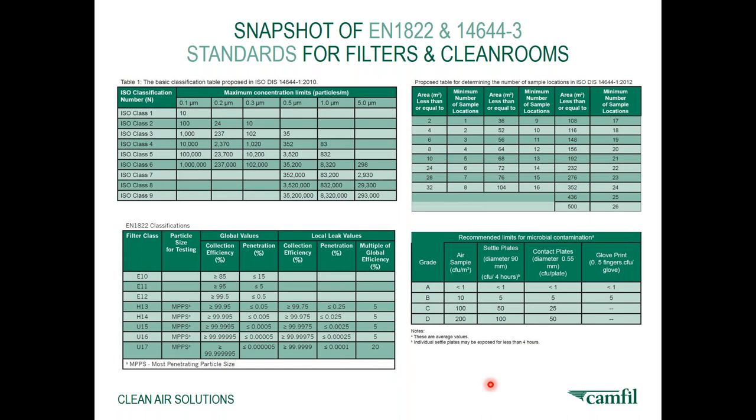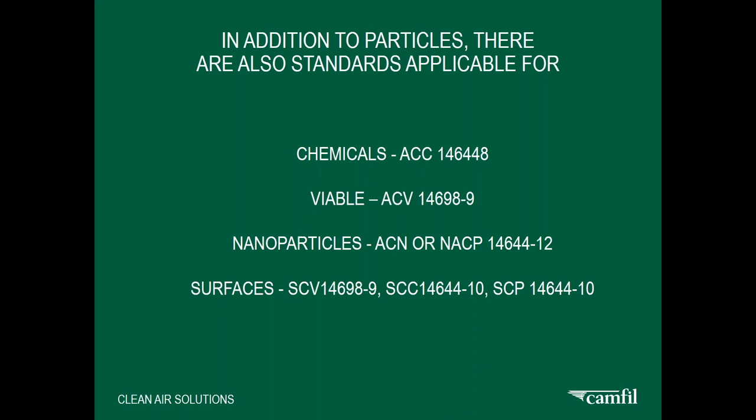Air cleaner is a perfect solution for ISO 7 to ISO 9 and where no laminar airflow is needed. Air cleaner filters are equipped with an H13 filter and have a filter efficiency of 99.95% at least. In addition to particles, there are also standards applicable for chemicals, viable particles, nanoparticles, and surfaces.